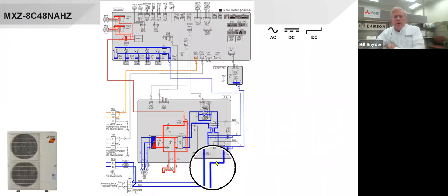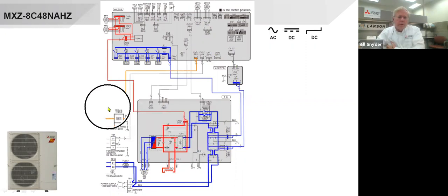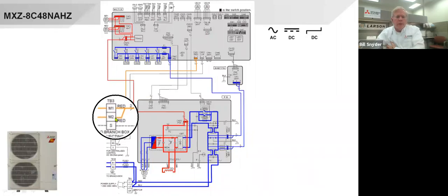Otherwise, we run the power out and we go through the noise filter section through here. We take a little bit of the 208, 230 volt, we run up to this board here. It's an MNET board. This is just taking that voltage down. I think it's 29 volts. It comes out, comes over and down through here and runs to the communication line right here. This is communication to the indoor branch box. And it's M1, M2 and a shield.